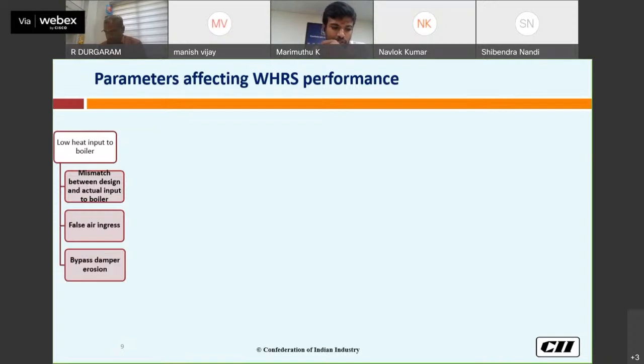And another one is bypass damper erosion. Generally we have a bypass damper for the WHRS, because it delivers heat for the raw mill drying, so we have to open some amount of air for drying. Also, if you want to maintain the temperature, in that case also we have to use the bypass damper. With bypass damper erosion, it is closed only when we record, but during normal operation if it leaks, it is allowing the waste heat to the ambient instead of power generation. So this is also one point.